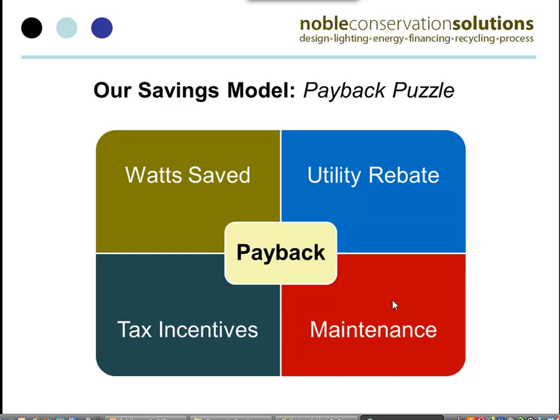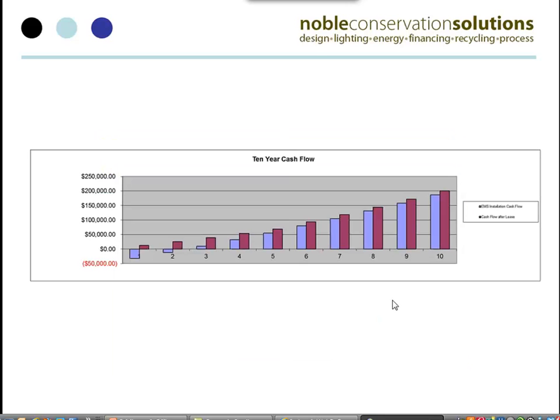We've had situations where people have been up on buildings doing some maintenance on a rooftop unit, a heating and cooling unit, and we come to discover that the person did not actually do that maintenance. They smoked a number of cigarettes up on the roof and then came back down, but did not switch out the filters and things like that. And obviously, that's a big waste for that company from an hourly expense standpoint. And just as importantly, swapping out the filters can save about 30% efficiency. So it's also a long-term cost savings over time. So again, that red corner, the maintenance, is a key piece of this payback puzzle.